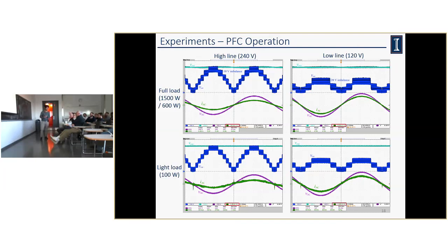Is that something that you require, to be in phase? Yes. For any grid-tied high power single phase AC converter, there is a power factor requirement. First of all, in order to reduce the VA rating of the converter, the power factor has to be as close to one as possible. The second is that if you have different power factors, there will be a lot of harmonics in the grid. Later I will show the typical limits of the regulation.